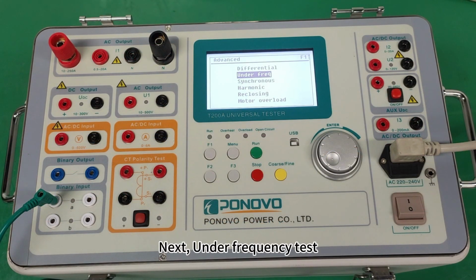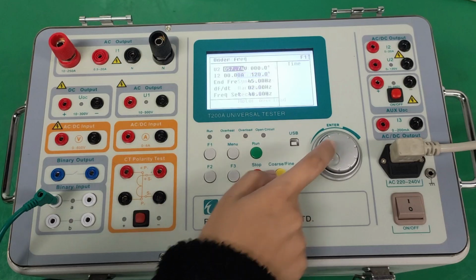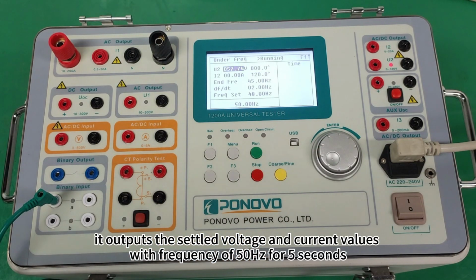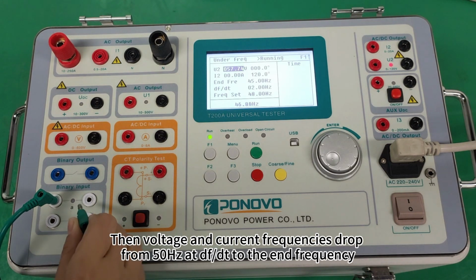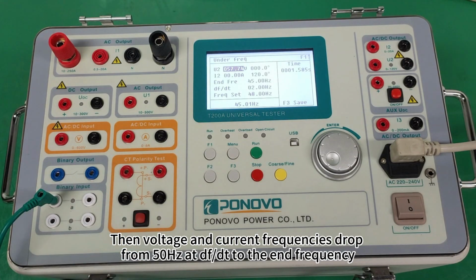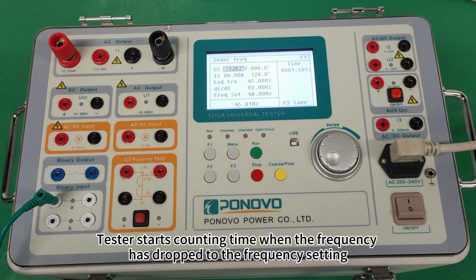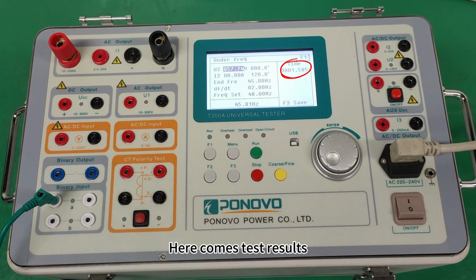Next, under frequency test. Press Enter button, press Run button. It outputs the settled voltage and current values with frequency of 50 Hz for 5 seconds. Then voltage and current frequencies drop from 50 Hz at df/dt to the end frequency. Tester starts counting time when the frequency has dropped to the frequency setting. Here come test results.